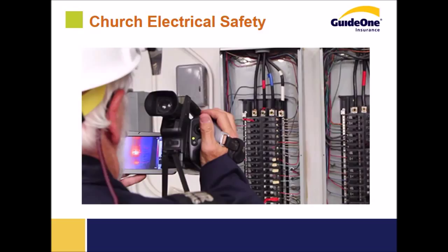This is an example of what goes into a thermography study. It usually takes 3 people: first, a certified infrared photographer running the camera, taking and storing images, and putting the report together. Second, an electrician to pull the panel covers off. And third, someone from the church to put a load on all the equipment—turning on air handlers, firing up air conditioner units—so any deficiencies will show up.